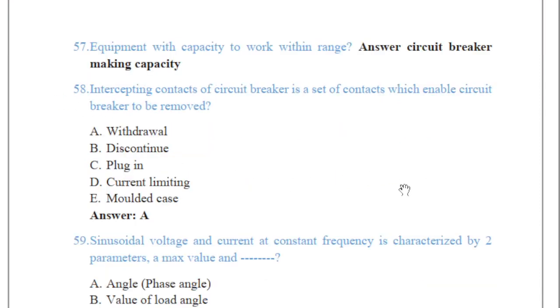Question 57 is asking about the equipment with capacity to work within a range — that is, circuit breaker making capacity. A circuit breaker is an electrical switch designed to protect an electrical circuit from damage due to overload or over-current, caused by over-current or short circuit. Its basic function is to interrupt current flow. The making capacity of a circuit breaker is the maximum current which the breaker can conduct at the instant of closing.